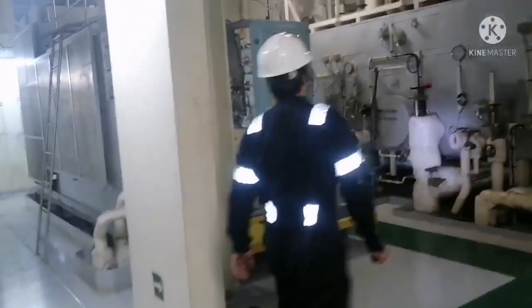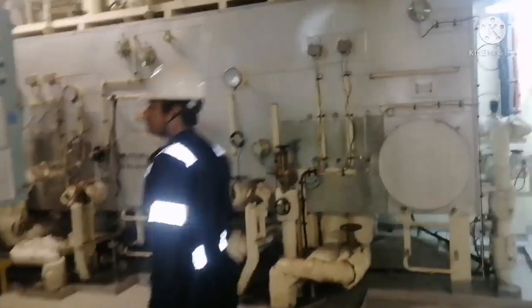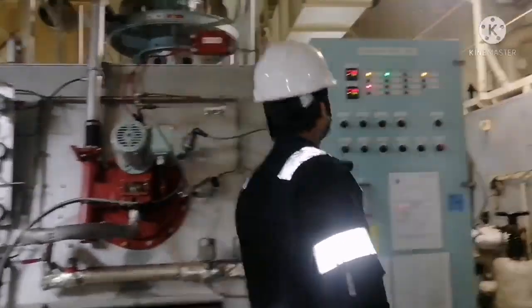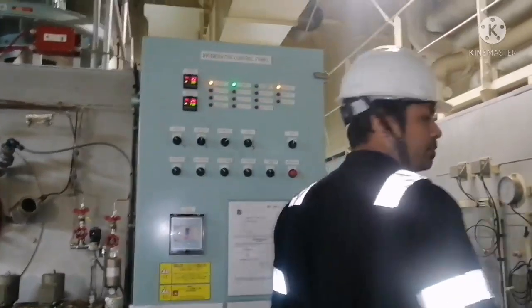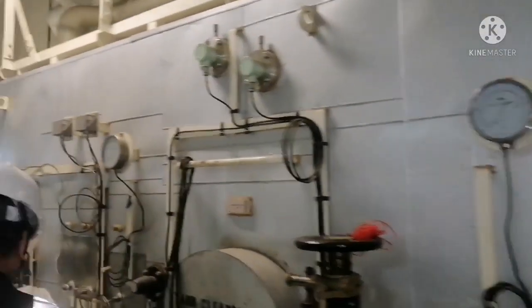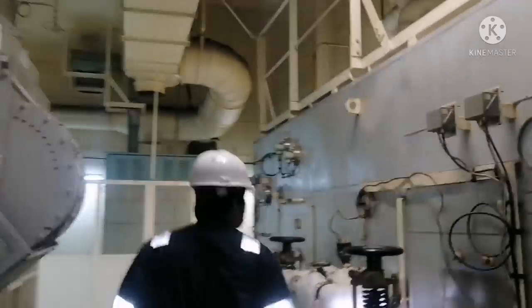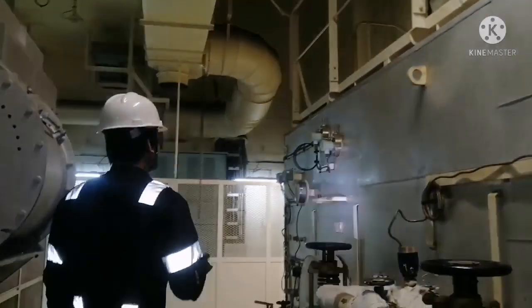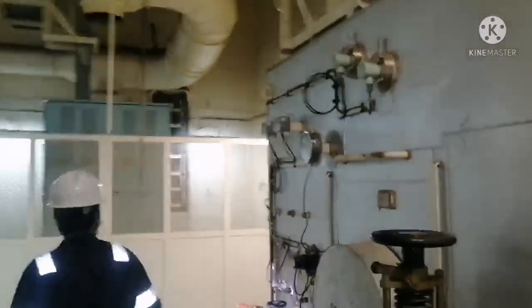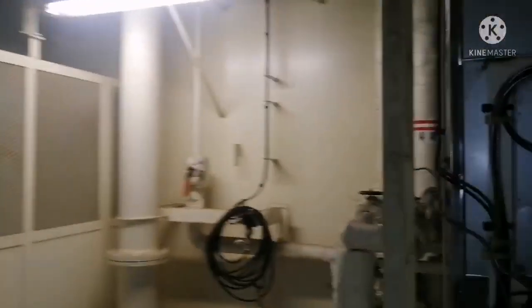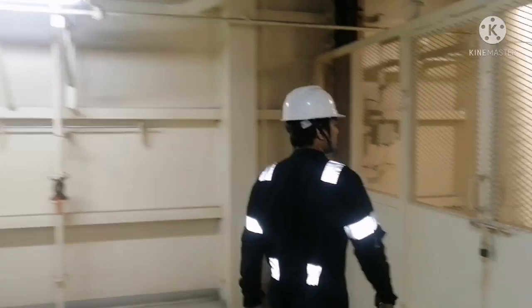So now I'm going to look at the incinerator panel. If there is any alarm, just reset it, close the fuel oil inlet valve, and just check the waste oil tank temperatures. If the temperature is high, close the steam valve so that you can avoid a high temperature alarm coming during your night time, so it doesn't disturb your sleep.